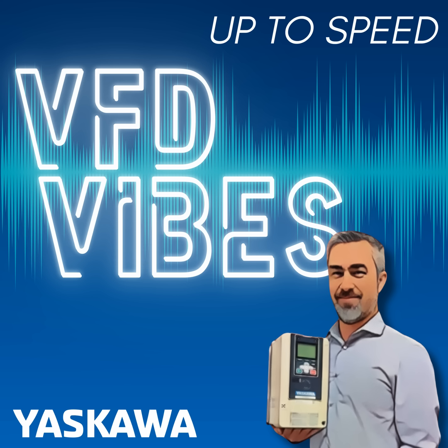Nope, go on. Okay, so now this thing called interrupting capacity is expressed in these units, AIC, which stands for amps interrupting capacity. So it's like a unit, right? It's like an inch or a volt or something like that. They're units. Okay. And these AIC units apply only to devices that are meant to interrupt. So a fuse is meant to interrupt. A circuit breaker is meant to interrupt. But a lot of other devices aren't. A terminal block isn't meant to interrupt, so it wouldn't have an AIC rating. A VFD isn't meant to interrupt.